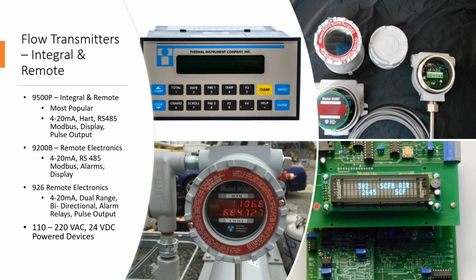The one thing I do want to stress here is that with thermal mass, and this is pretty much true with all thermal mass, all units are 4-wire devices. We are not loop powered. Because we are heating up a sensor, we actually need to power the unit. So that means we need 4 wires: 2 wires to power the unit and heat the sensors up, and the other 2 wires will power that 4 to 20 loop to bring that information back to your control room or PLC. I just want to state that because that's one of the questions I typically get a lot: I'm looking for a loop powered device with 2 wires. Well, in our situation, you will need 4 wires.